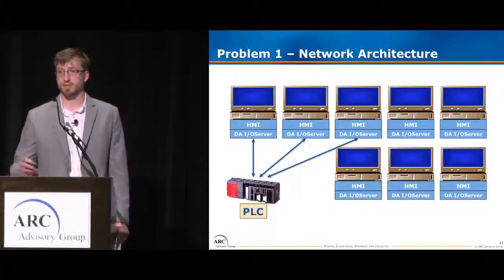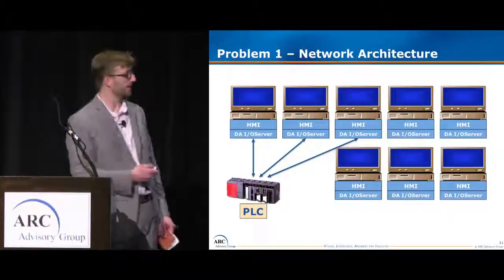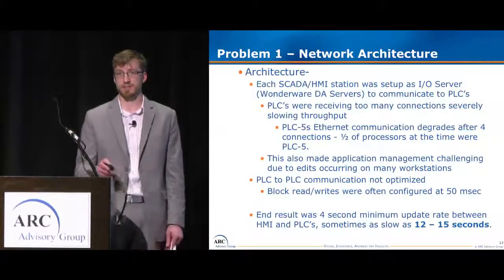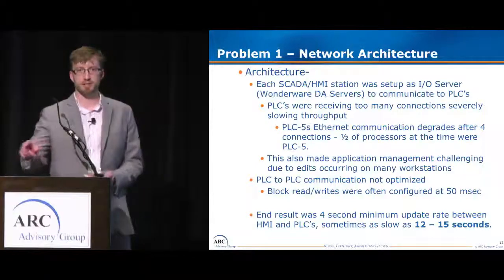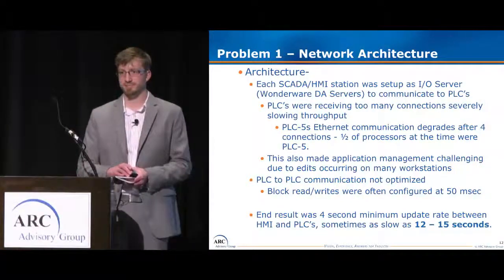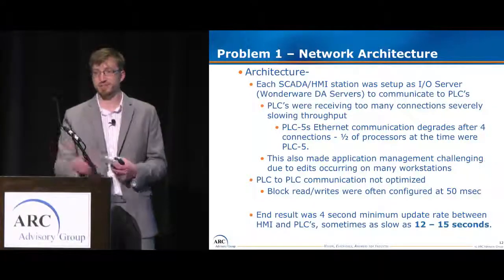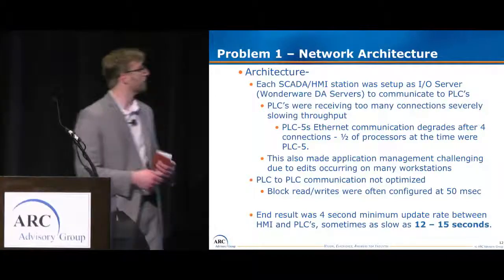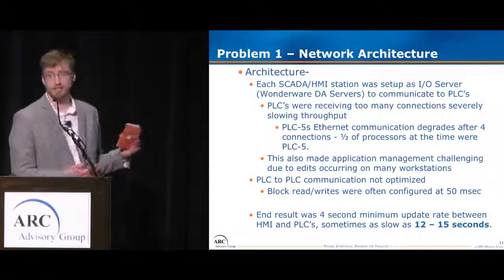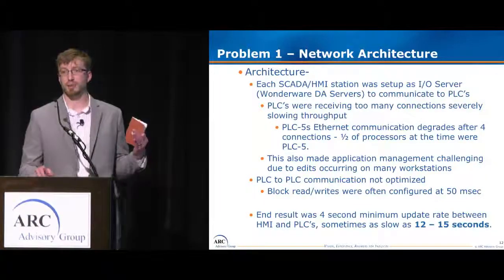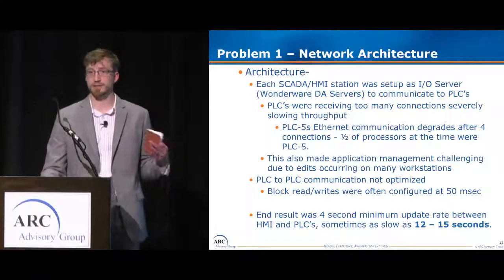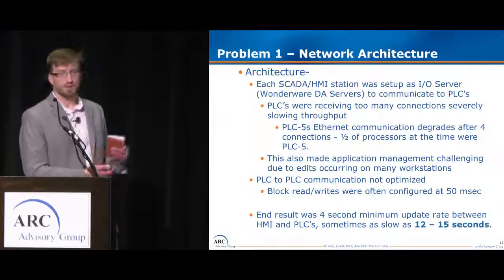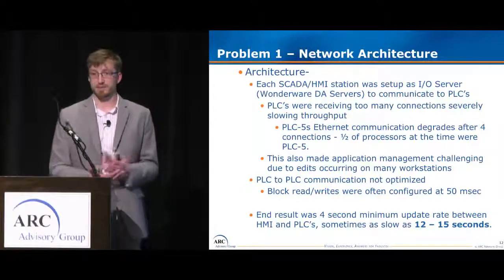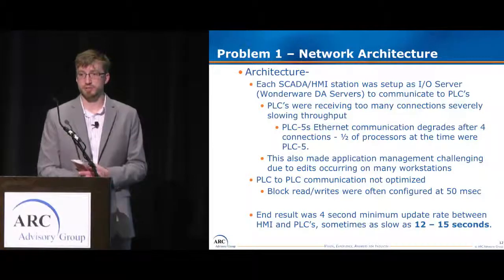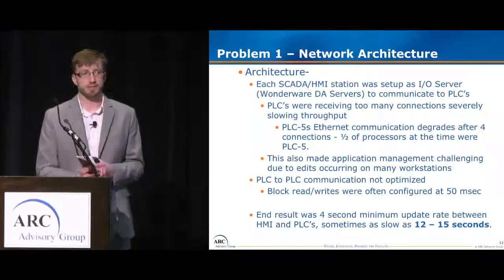When your operator starts trying to run machinery from the HMI, you have huge delays. And what does an operator do when he hits a button on the HMI? Does he sit and wait for something to happen? If nothing happens, he wants to hit it again and again. And what we were experiencing, it was pretty common to see a 4-second delay between operator action and something happening in the PLC. And the legacy PLCs have some constraints. It's older technology, and we found that with PLC 5s, after 4 connections, the performance is severely degraded.